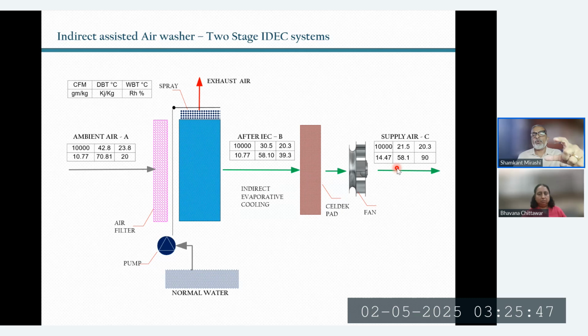Now, if I have evaporative cooling, which is giving me 26 degree air, and I have another technology which is giving air at 22 degree, and I have to remove the same amount of heat load from the space, those who are comfortable with HVAC design will realize that with evaporative cooling, I would have required 1 lakh CFM, 1 lakh cubic feet per minute. That's the amount of air that would have been required, because I was offering the air at 26 degree. Now, since I'm getting air at 22 degree, lower temperature, I can pick up the same heat at maybe 70,000 CFM. So I can reduce the capacities of the ventilation systems on day one. So instead of a 1 lakh CFM blower, I can do the same job with a 70,000 CFM blower. We cut down, it could be 30, 40 kilowatt avoided on day one, right? So that's the kind of benefit that we can offer here.